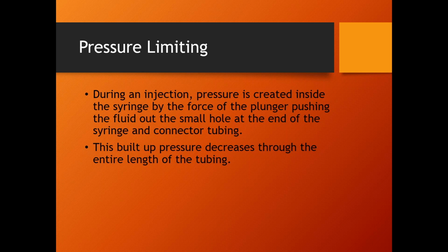And another important thing, that 300 PSI is in the syringe, all right? That is not in the patient. Anybody work with infusion pumps? Mess around with infusion pumps? All right, what's the occlusion alarm pressure on a typical infusion pump? It's like 12 PSI, right? Somewhere in that range. So in an infusion pump, if the system senses that the pressure has gotten over 10 PSI, it stops the infusion, alarms go off, the nurse comes over, fixes whatever the issue is, and fires it back up, all right? So no, we're not gonna fire 300 PSI into a patient.